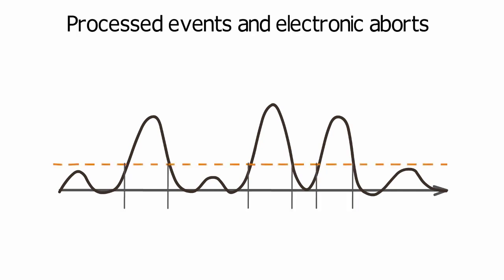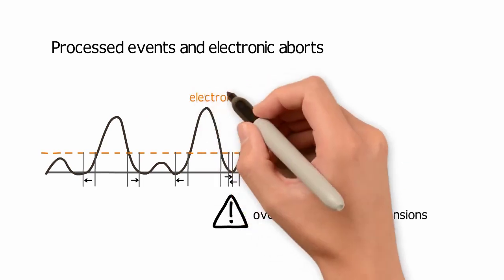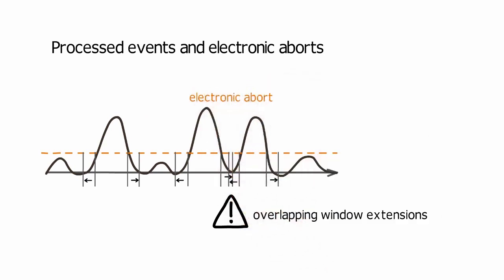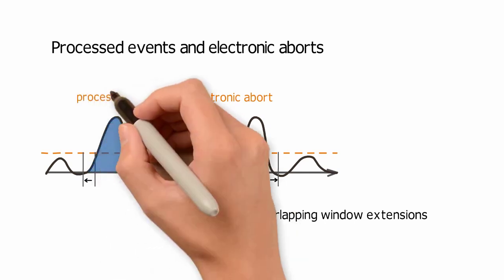When running sample at a high event rate, the cells might arrive at the laser very close to each other. If two pulses are close enough that the window extensions overlap, those signals cannot be processed and both are discarded as an electronic abort. Voltage pulses that are well separated from neighboring pulses will result in a processed event.